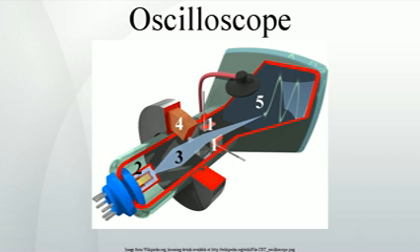The trigger section controls the start event of the sweep. The trigger can be set to automatically restart after each sweep or it can be configured to respond to an internal or external event. The principal controls of this section will be the source and coupling selector switches. An external trigger input, EXT input, and level adjustment will also be included.